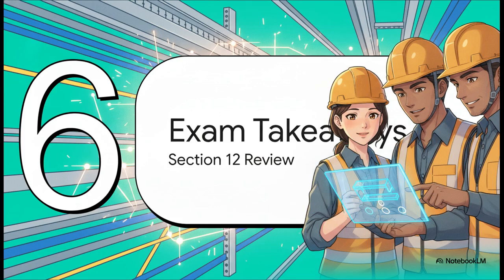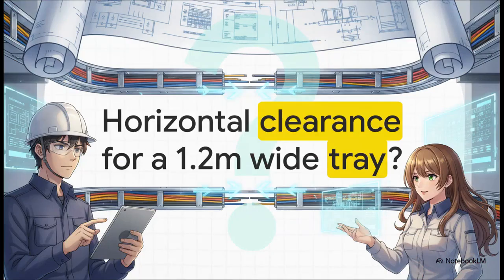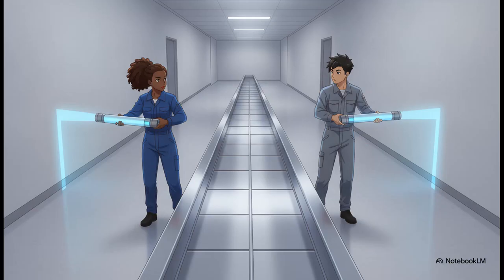Finally, Section 6, Red Seal Exam Takeaways. All right, I am shifting fully into exam coach mode right now. Let's test your retention with a highly realistic Red Seal scenario. You're reviewing a blueprint and you notice a massive cable tray run. What is the minimum horizontal clearance for a cable tray that is 1.2 meters wide? Take a second. Think back to the clearance tables we just discussed. Did you get it? The answer is 600 millimeters on each side.